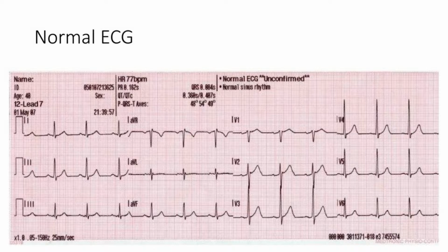All right, great. I also wanted to add, in terms of filtering, electronic devices. Sometimes patients still have their phones on them, and that can also interfere with the ECG baseline. And rightly, you mentioned the generator bit of it. So we just need to troubleshoot again and again to make sure we get a very clean ECG. Tampering with the filter settings to get a smooth ECG should be one of last resort, because when you do that, you compromise the diagnostic capability. The wider it is, the more likely you are to get findings picked up, but leaving it very wide exposes your ECG to a lot of artifacts.